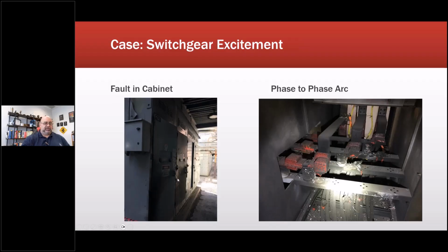When they were brought in, he survived, he was fine. He was wearing the right equipment and everything, so minor injuries. They had to go in and clean it. They used contact cleaner on all the soot on all of the insulators. Now these are ceramic, and just to put it into perspective for how hot it got, these melted. That's not melting from the rubber, that's melting from the ceramic. I brought one of those back. They gave me one of these as a souvenir, and I had it in the office for a bit until one day it fell over, cracked, and all of the ceramic inside had turned to powder. So it was that hot, and all this rubber stuff had dripped everywhere, and you can see arc holes in different spots from where it arced here.